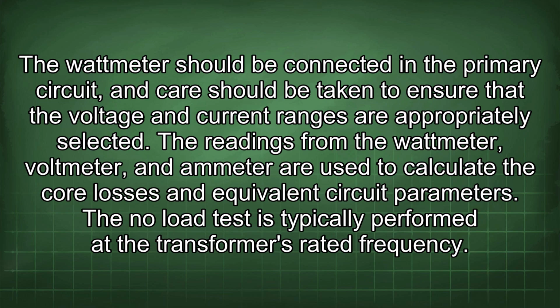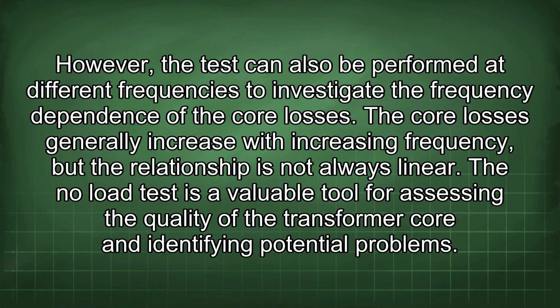The no-load test is typically performed at the transformer's rated frequency. However, the test can also be performed at different frequencies to investigate the frequency dependence of the core losses. The core losses generally increase with increasing frequency, but the relationship is not always linear.